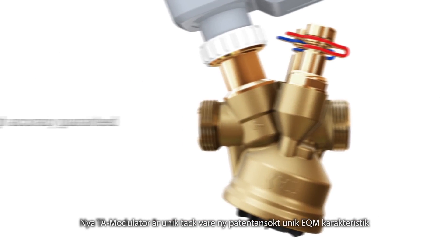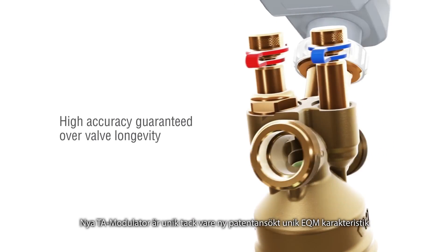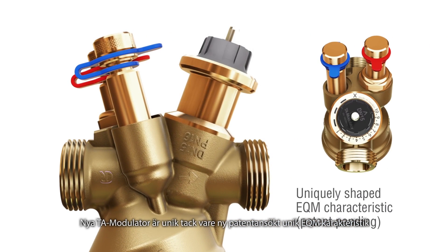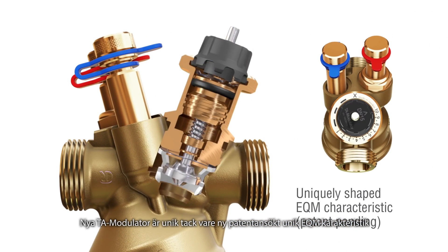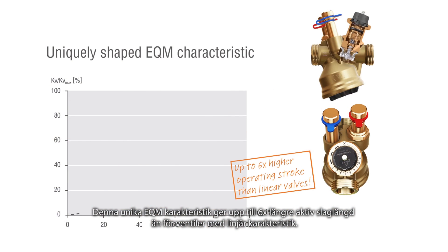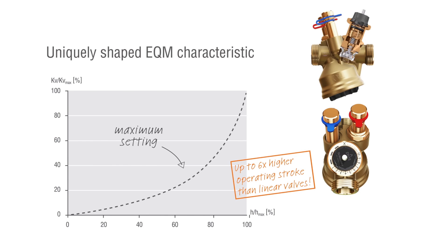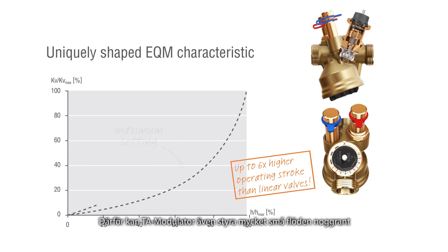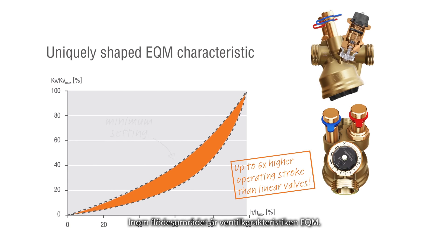The new highly precise TA Modulator is unique due to its new patent-pending uniquely shaped EQM characteristic. Its uniquely shaped profile provides an up to six times higher operating stroke than linear valves. Therefore, TA Modulator is able to precisely control also very small flows. The new characteristic remains equal percentage within the range of maximum and minimum flow settings.